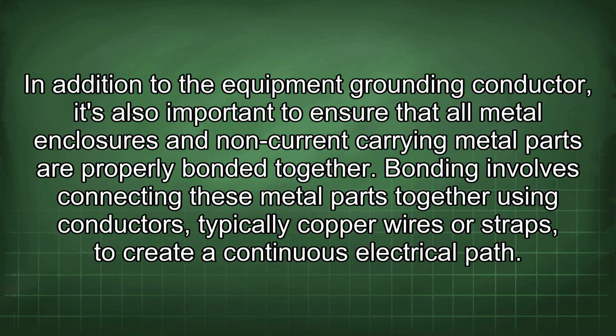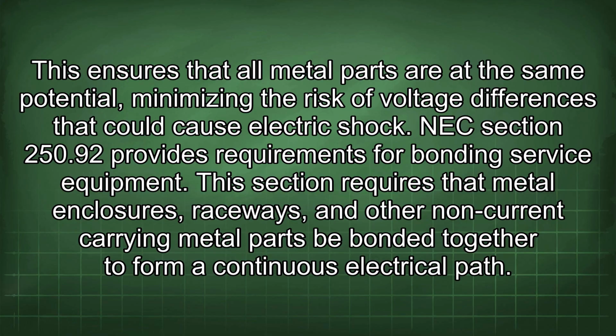In addition to the equipment grounding conductor, it's also important to ensure that all metal enclosures and non-current carrying metal parts are properly bonded together. Bonding involves connecting these metal parts together using conductors, typically copper wires or straps, to create a continuous electrical path. This ensures that all metal parts are at the same potential, minimizing the risk of voltage differences that could cause electric shock. NEC Section 250.92 provides requirements for bonding service equipment. This section requires that metal enclosures, raceways, and other non-current carrying metal parts be bonded together to form a continuous electrical path.